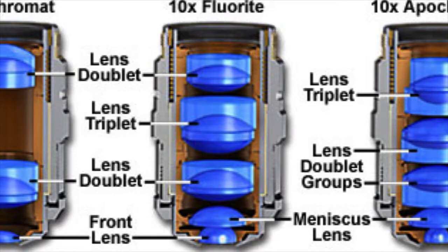Remember, fluorescence microscopy is a low light level process. We're using reflected light, reflecting light off our specimen, and expecting the emission light from the specimen to come through the objective. If we use standard achromats or plan achromats, these objectives tend to absorb a lot of light. Manufacturers have discovered a type of glass called fluorite glass, which is highly transmissive in these low light levels we're using for fluorescence microscopy. Most objectives on the confocal microscope are fluorite objectives designed for high transmission of light.